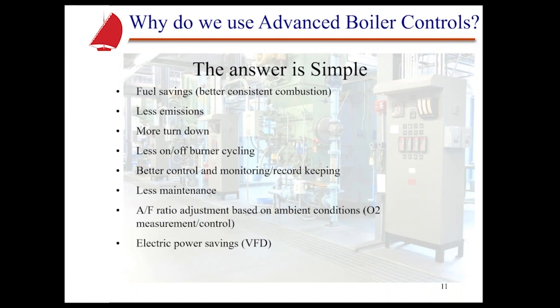Also, with this type of system, we can bring a variable speed drive into the control scheme. And this is where the combustion air fan can be modulated. All of these fans have been designed, or sized, if you will, to make sure that this particular burner will make rate. And that motor is going to run normally at synchronous speed, in other words, across the line. So it's going to be turning at just under 3,600 RPM, and therefore requiring that type of amperage, if you will, to do that.